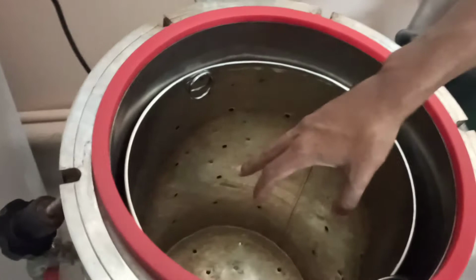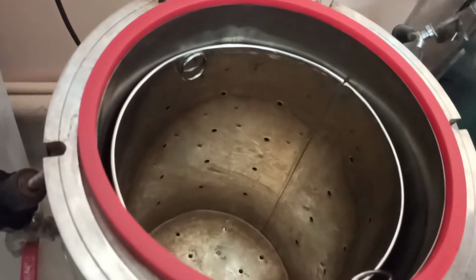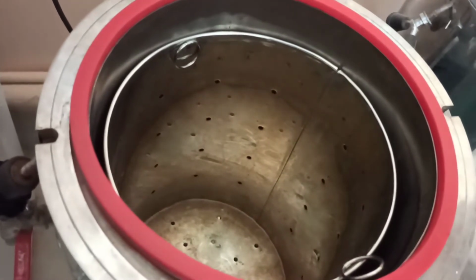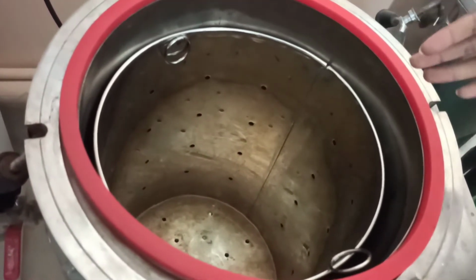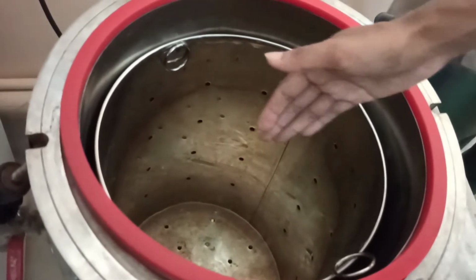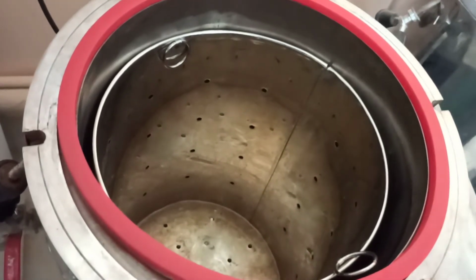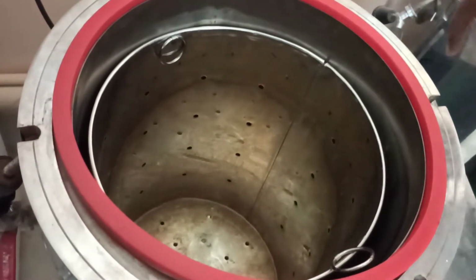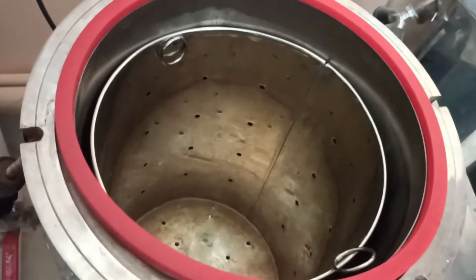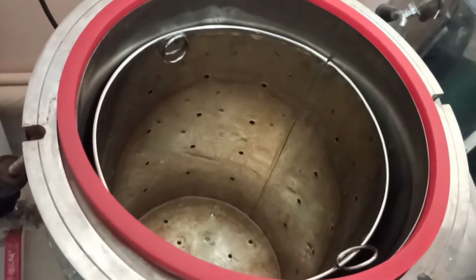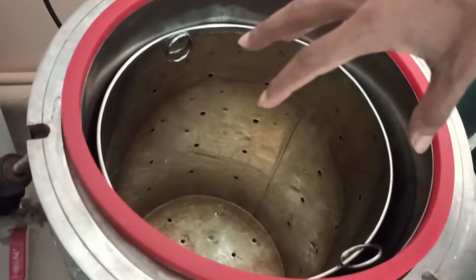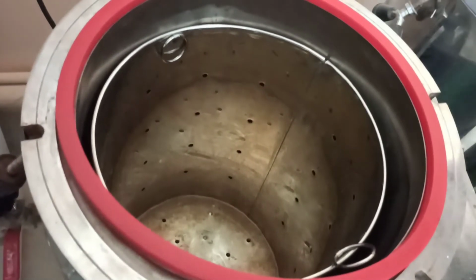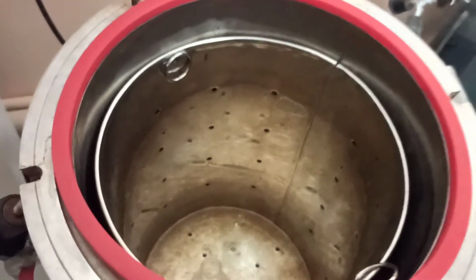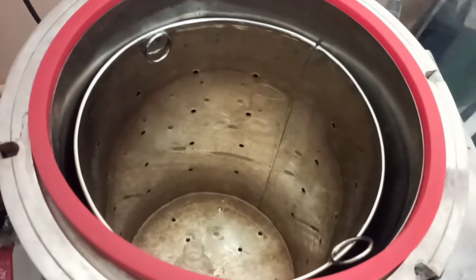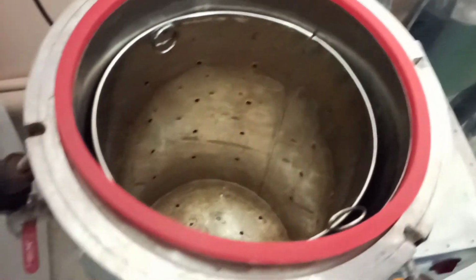Then we have to fill a sufficient amount of water inside the inner chamber of this autoclave. The water level should be accurate. If the water level is lower than required, the heater present below this inner chamber will start malfunctioning. If excess water is present inside this autoclave, it will hinder the process of sterilization. After filling the inner chamber with sufficient water, we place the glassware or any other materials to be sterilized inside the autoclave chamber, and we close the lid.